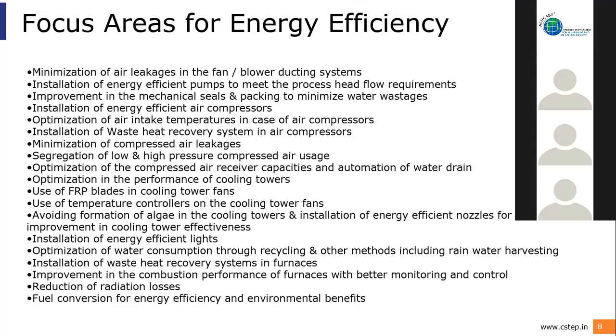Lighting is another area which has some scope in energy savings. Waste heat recovery: as was said, there is a potential of waste heat. Even if waste heat recovery systems are installed, like recuperators or APHs, the efficacy of these waste heat recovery units needs to be evaluated, and there is tremendous potential for that.